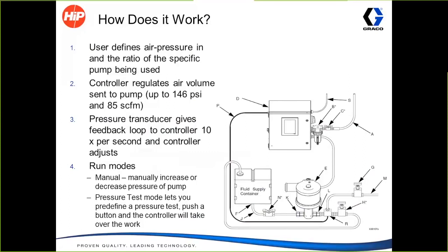And then when we achieve that pressure, we'll do various things, like we could hold the pressure, we could do a decay test. There's a few options that we could do. As far as input air pressures, we want to make sure that we can supply enough pressure to run any pneumatic intensifier pump that's out there, and that's a pressure and a flow requirement. So we can handle air pressures up to 146 psi and also 85 SCFM. So that should be plenty of air pressure and flow to run typical pneumatic intensifier pumps that you see in the field.